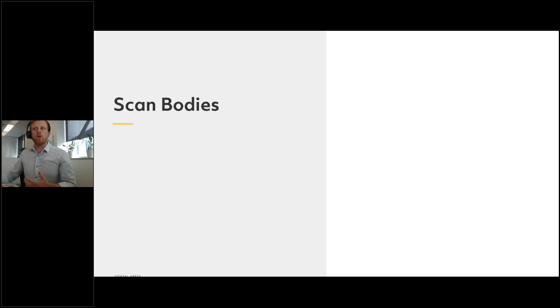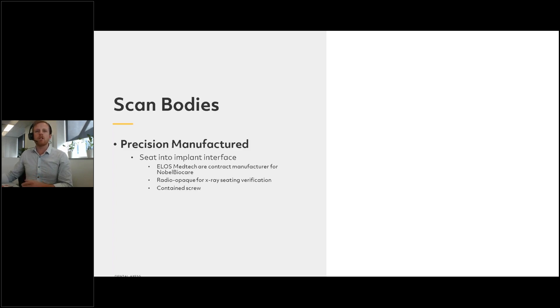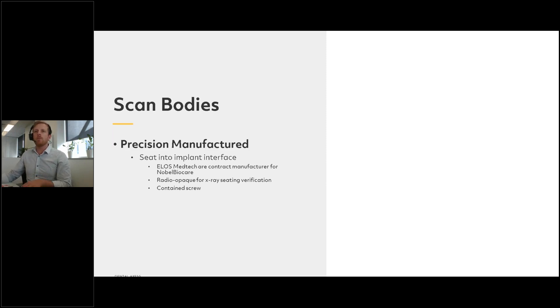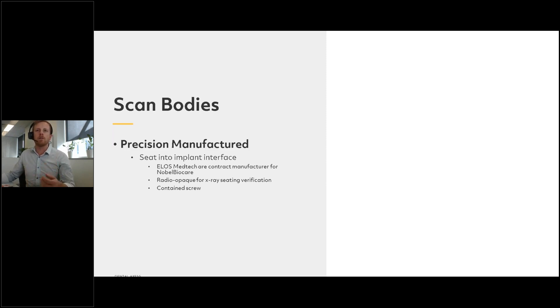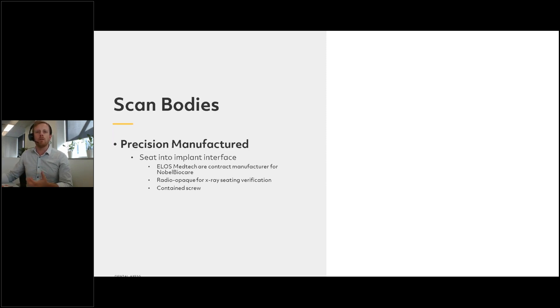Scan bodies are precision manufactured to seat into the implant interface, whether you've got a trilobe, a hex, or some other interface. For example, ELOS Medtech are a Swedish company who contract-manufacture for Nobel Biocare — because they contract-manufacture, they know very accurately the dimensions of the implant interface, hence they can create a scan body that will interface perfectly with the implant. They're radio-opaque for seating verification and typically contain a screw so you can ensure the scan body is seated correctly.